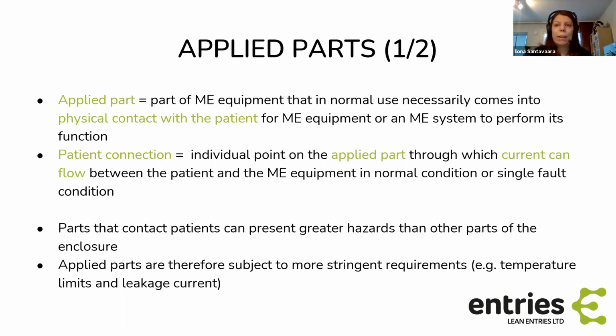And as promised, applied parts is one of the classifications that we'll look at in more detail. So it's basically part of medical electrical equipment that in normal use necessarily comes into physical contact with the patient for this device to perform its function. And patient connection is an individual point on the applied part through which current can flow between the patient and ME equipment in normal condition or single fault condition. So patient connection is sort of a subclass of this applied part. And then any other surface parts that are not applied parts are enclosures in the standard.